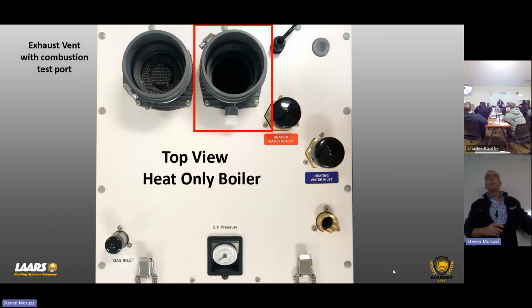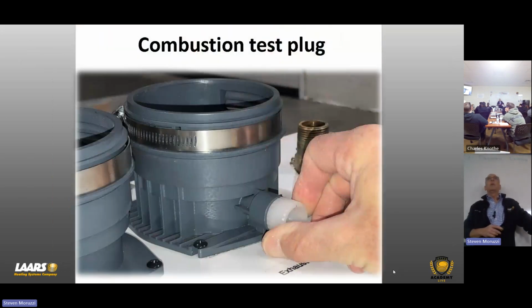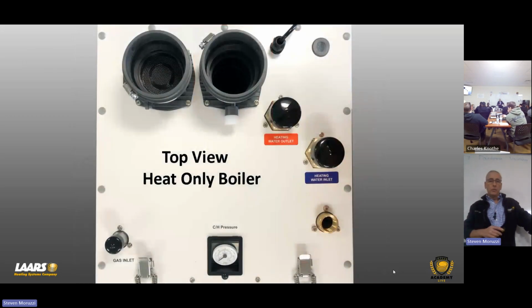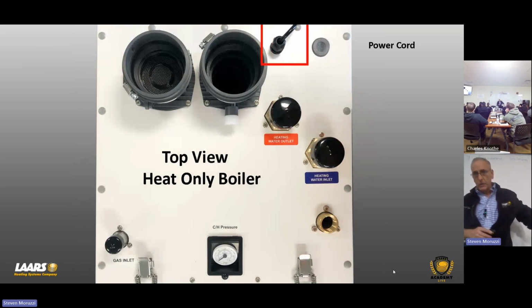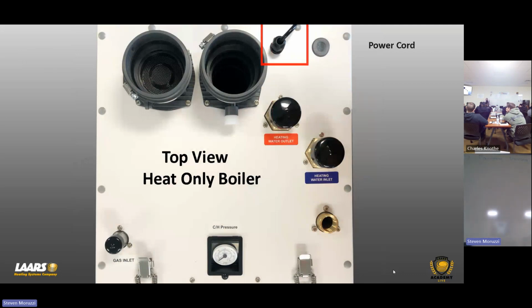We have the outlet flue with a test port right there for your combustion analysis. And again, every manufacturer requires a combustion analysis over 85%. This is an appliance, so it does have a power cord that you would plug into a GFI outlet or GFI breaker. The outlet that's in the cabinet for that condensate pump is non-GFI.